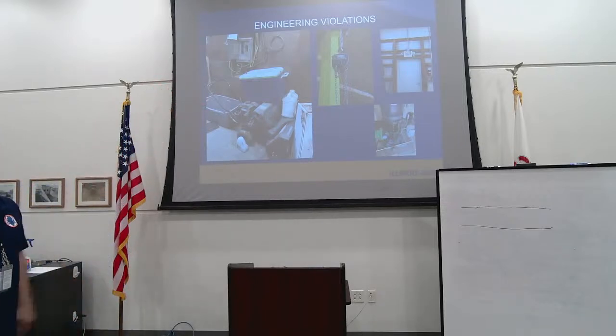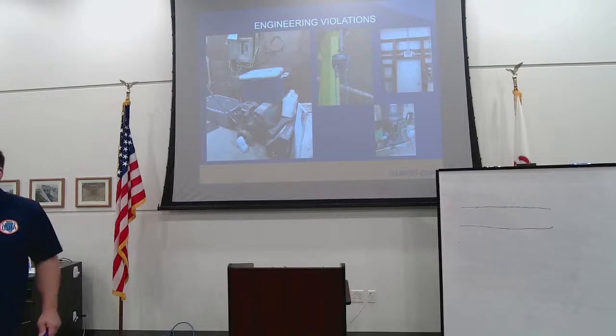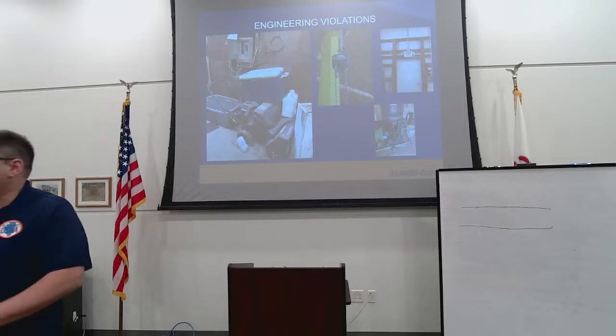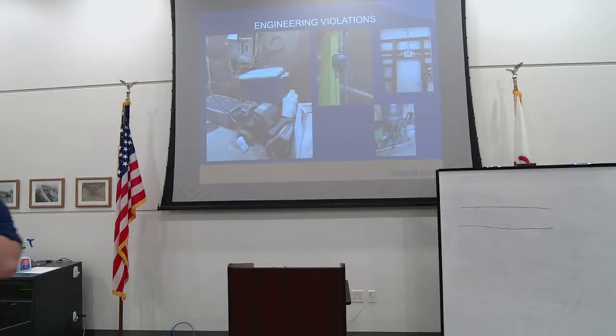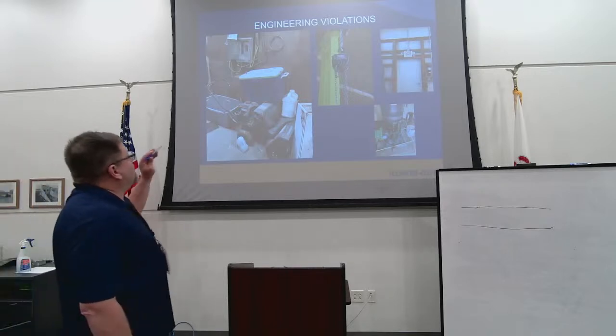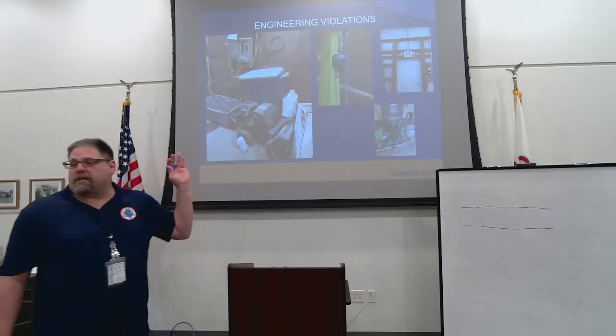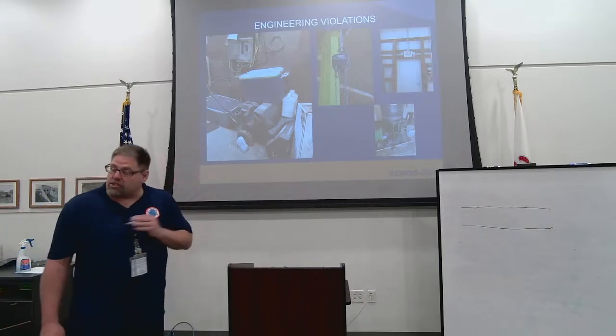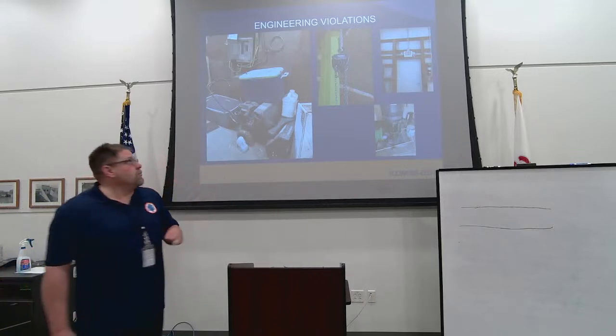And why might he fall or she might fall and trip? Because this is a violation right here. You can't have things in front of your electrical panels. That's across the board. We cite everybody for that constantly. You have to keep open space in front of your electrical panels. The general rule of thumb is 30 inches or the width of the equipment.